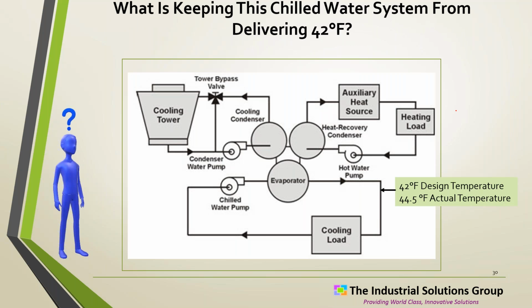Start putting yourself in the mind of an average technician or operator out there, and that chiller is just a single piece of equipment, but it can't run without, in this case, 3 pumps running. It's got a cooling tower, and every one of these pieces of equipment can go bad and will go bad with time. You know, cooling tower water could be too warm. Well, you aren't going to get chilled water if the cooling tower is too warm. Your pump, is it okay? Not okay? Fouled surfaces because of poor water treatment systems.